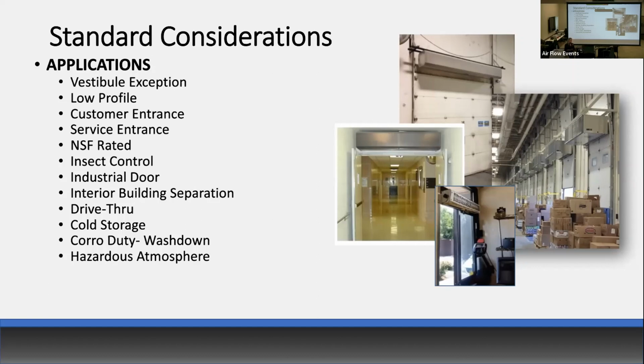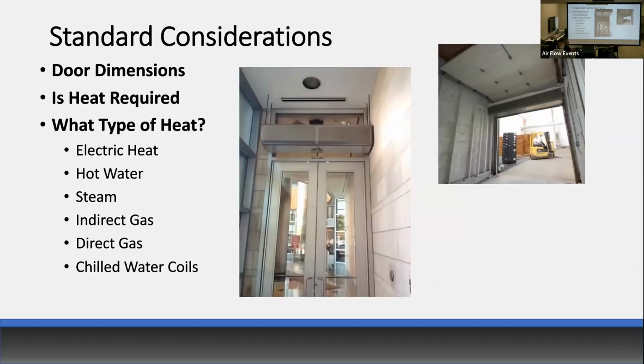Cold storage, we also get into wash down environments as well as hazardous duty. So pretty much any kind of application, there's an air curtain for it. Other standard considerations, door dimensions. If you are calling asking about an air curtain, first thing we're going to ask is what's the width and height. Some people will try to oversize the air curtain, making it wider than the actual opening. You don't need to do that. You just need to make sure you're covering the amount of the doorway or window that opens.